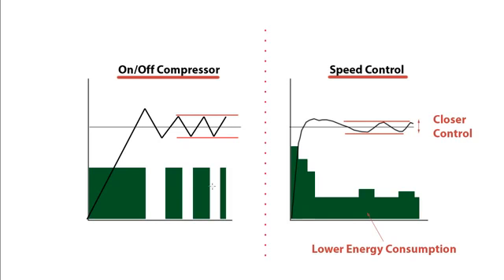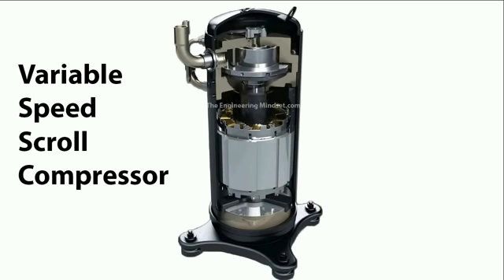Now normal cheaper compressors, as you can see here on the left, will just switch on and off to try and maintain the load. As a result, you'll see it's constantly under and over swinging or shooting, giving pretty poor control, and also obviously a much higher energy consumption. Whereas with the speed control compressor, you get a much tighter control, and that results in much lower energy consumption operating throughout. So the inverters also provide soft starts whenever the VRF system comes online, and this means you don't suffer from high inrush currents, which can damage your electrical distribution throughout the building and also result in high penalty fines from your electrical distribution supplier.